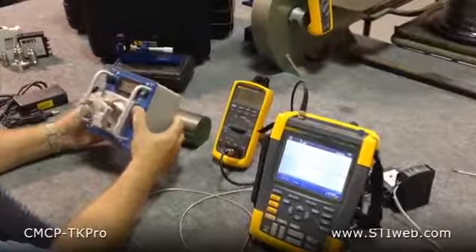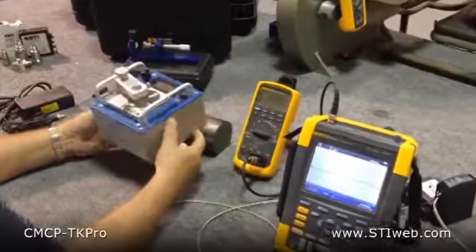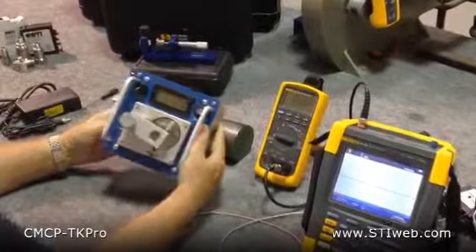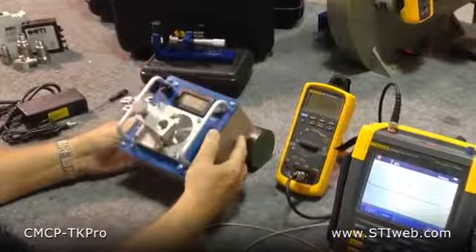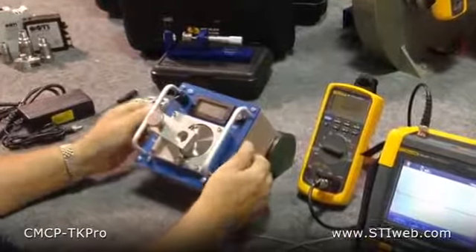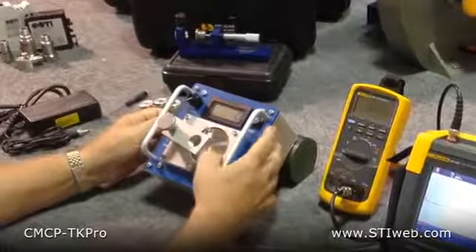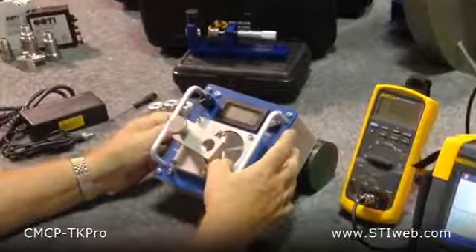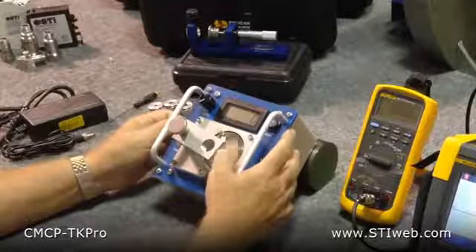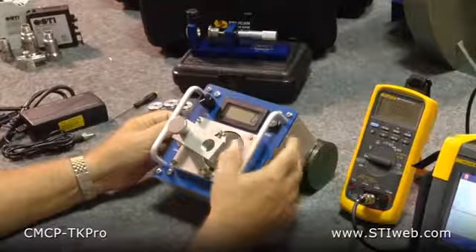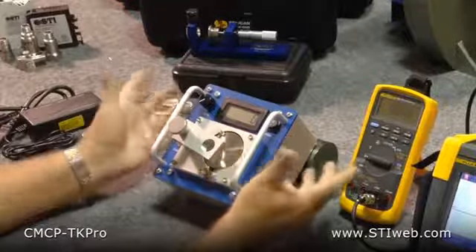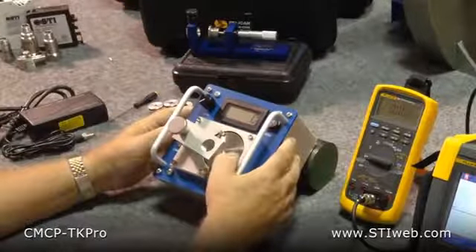All right, we're real proud of our new CMCP TKPro. Some people call it a wobulator. Its purpose is to provide a fairly calibrated signal into an eddy probe or proximity probe system to verify your monitoring performance and that everything is working correctly. In other words, end-to-end testing.